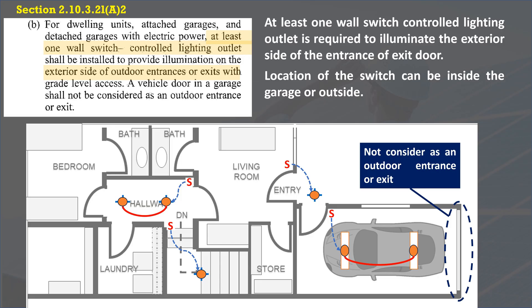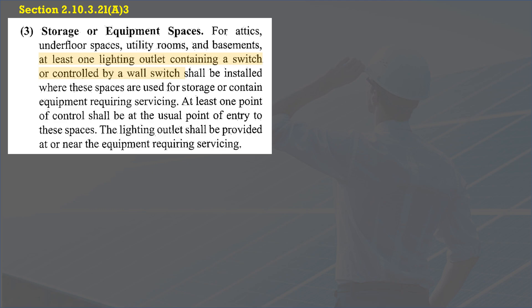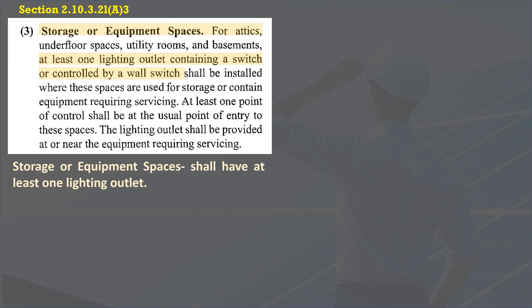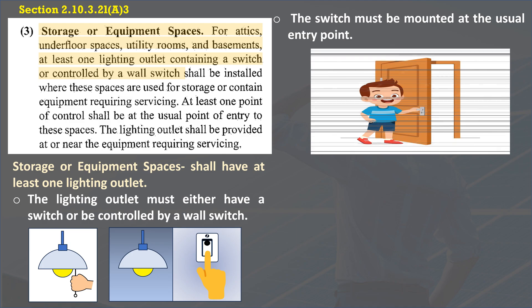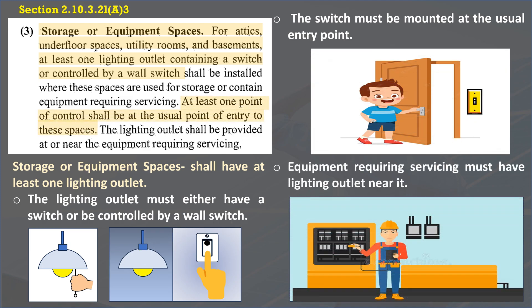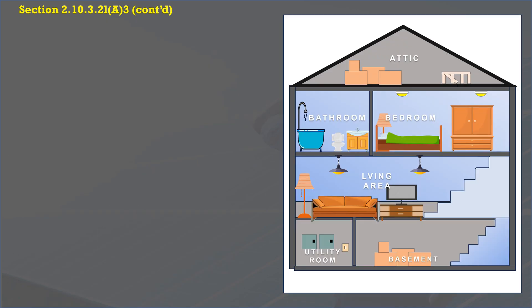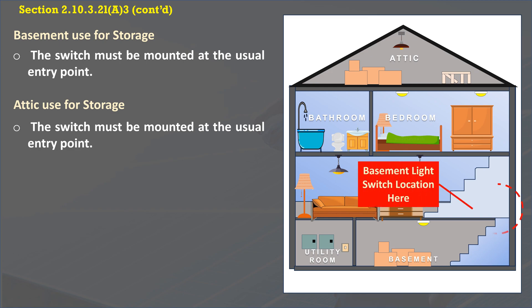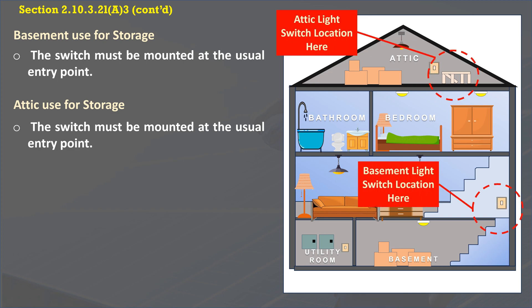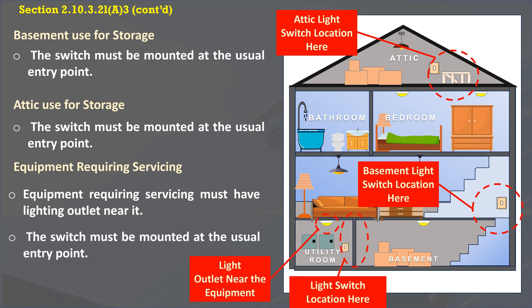At least one lighting outlet is required in areas of dwelling units used for storage or equipment space requiring servicing. These include attics, underfloor spaces, utility rooms, and basements. The lighting outlet must either have a switch or be controlled by a wall switch. The switch must be mounted at the usual entry point, while equipment requiring servicing must have a lighting outlet near it. A utility room with a piece of equipment requiring servicing must have a lighting outlet installed near that equipment.